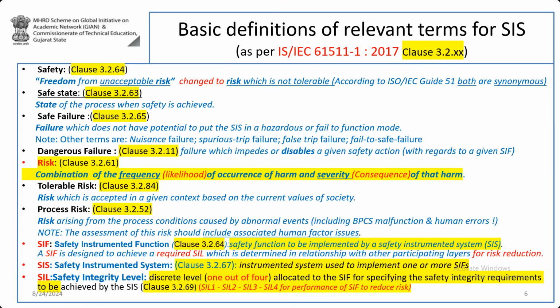SIL is a discrete level, 1 out of 4, allocated to SIF for specifying safety integrity requirements, meaning the requirements to be achieved by SIS. 1 out of 4 means there are SIL 1, SIL 2, SIL 3, SIL 4. This is what I have elaborated. So SIF can have SIL 1, SIL 2, SIL 3, or SIL 4. In short, these are the various levels assigned to SIF.